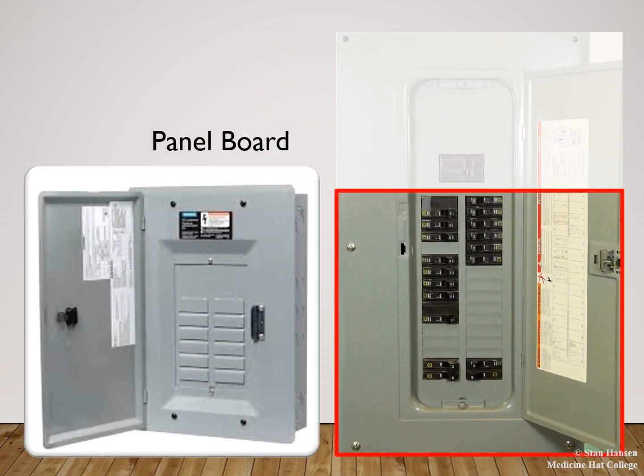The panel board is the circuit breaker compartment. So usually this is the second half of our combination panel, so the lower half of the panel, or it could be a separate panel or a sub-panel within the house. If your house has a secondary panel inside the garage or maybe a secondary panel inside the basement, these are both considered to be part of the panel board.